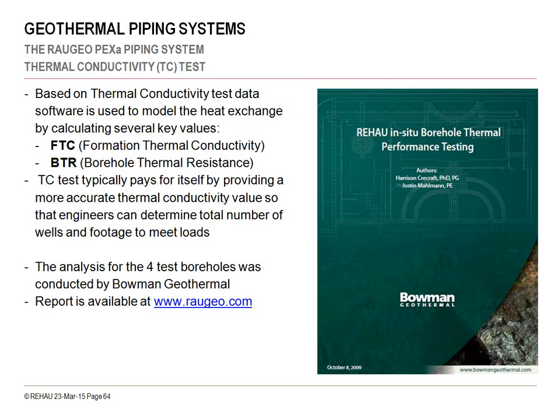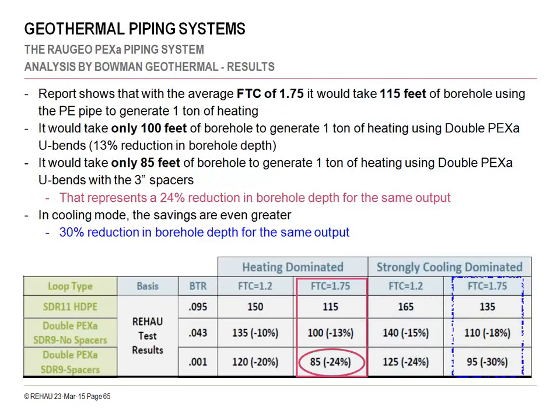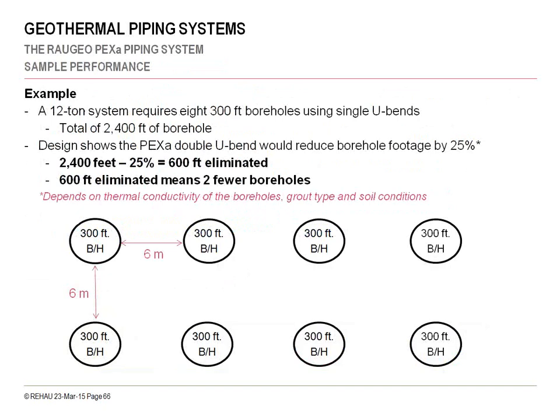But this report is showing that in the area of the double U bends with the spacers compared to the single U bend of Hdpe, in a heating dominant project there'd be about a 24% difference in heat exchange, and in a cooling dominant, which would be typical of commercial application, a 30% reduction. Testing has also been done by Oak Ridge Laboratories, validating these additional heat exchange for the double U bends. So what does that mean? If you have a 25% additional heat exchange, it means that in this case you're able to take a couple of boreholes off of the project.